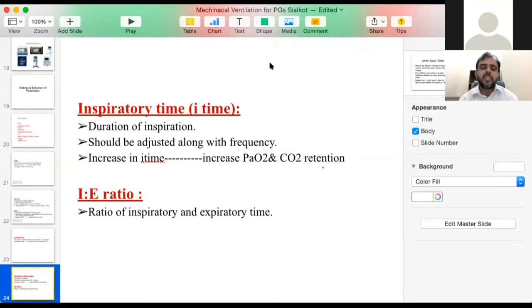Okay, so this is the normal ratio. If you reduce the respiratory rate, then you are providing more time for a respiratory cycle, and then the IE ratio will change. But this is the normal ratio. We can increase, if we need, inspiratory time to 1 second and expiratory time to 1 second. We can further reduce inspiratory time to 0.6 second. So according to the need, according to the condition of the patient, we can modify.